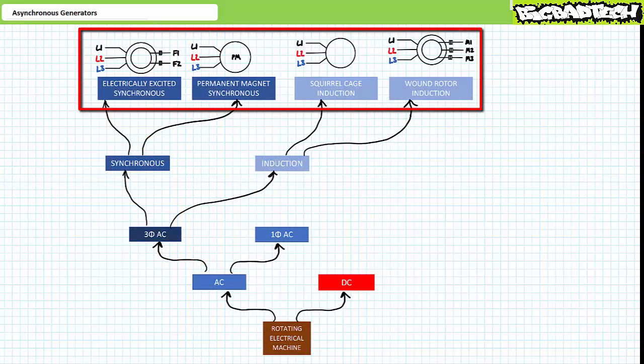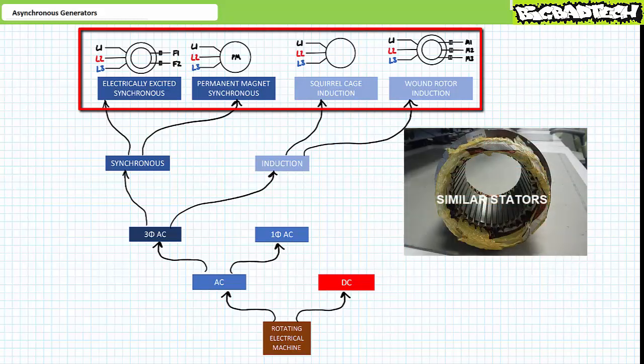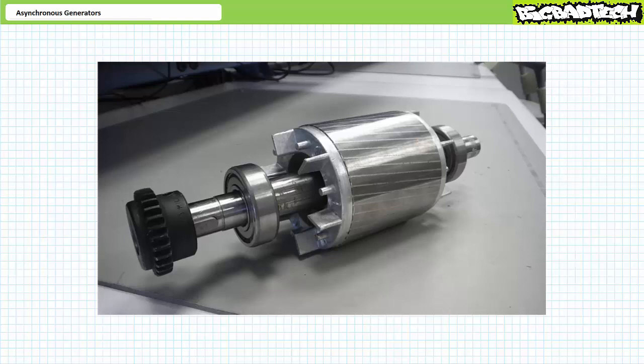If we go further into specifics about these four main types of three-phase AC generators, we find all of them possessing stators essentially indistinguishable from one another. Really only the design of the rotor physically distinguishes one type of machine from another. The rotor of an asynchronous generator is constructed exactly like the rotor of a squirrel cage induction motor — a cast aluminum or copper cage-like structure often embedded in laminated sheets of iron designed to concentrate the magnetic field. These types of rotors are mechanically simple, necessitate no external electrical connections, making asynchronous generators reliable and inexpensive. In fact, an off-the-shelf squirrel cage induction motor can be used as a generator with little if any modification.